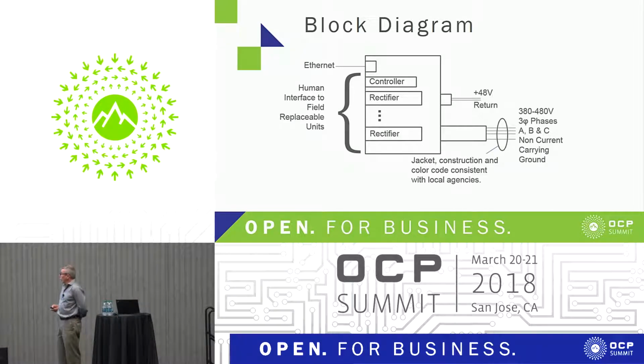In terms of a block diagram, you've got the Ethernet connector on one side, the system controller, which is just a microprocessor controller that talks to the rectifiers, as well as talking to the Ethernet external. 4 rectifiers plug in. They're obviously field replaceable units. They're hot swappable. The controller knows how many modules there are there, so that you can interrogate the controller for capacity, as well as health. And then on the back side, 3 phases, 4 wires, 3 individual phase wires, and non-current carrying ground coming in there in that whipcord.